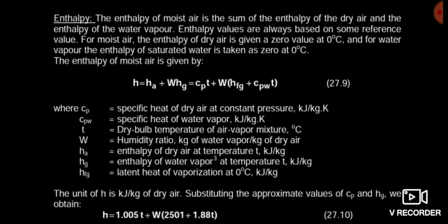You should remember that the temperature used in enthalpy must be in degree Celsius, not in Kelvin. I am focusing on this because in further lectures we will see that somewhere we consider temperatures in Kelvin. But here in case of enthalpy, we consider the temperature in degree Celsius: H equals Cp·T plus W into (HFG plus CpW·T). This total is the enthalpy of moist air.